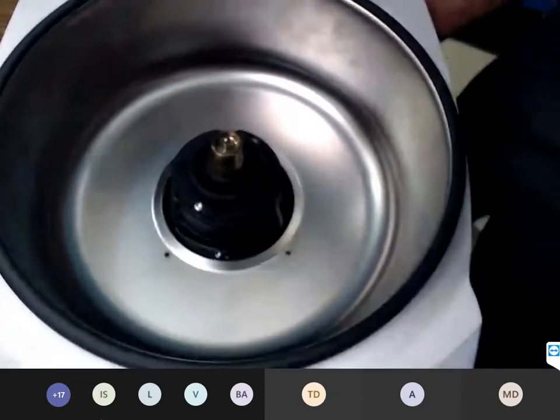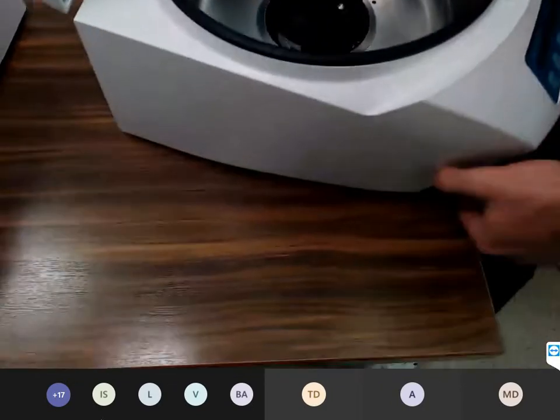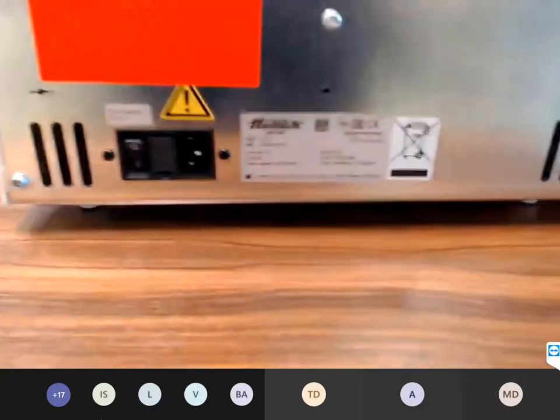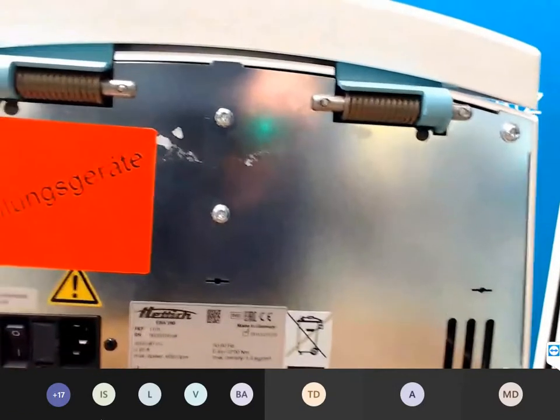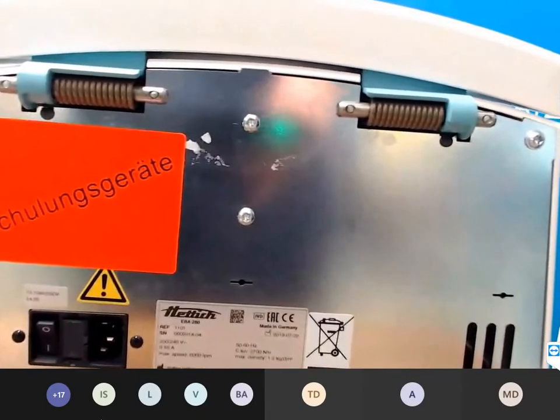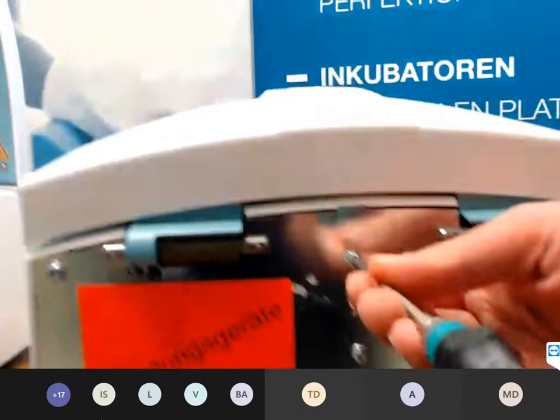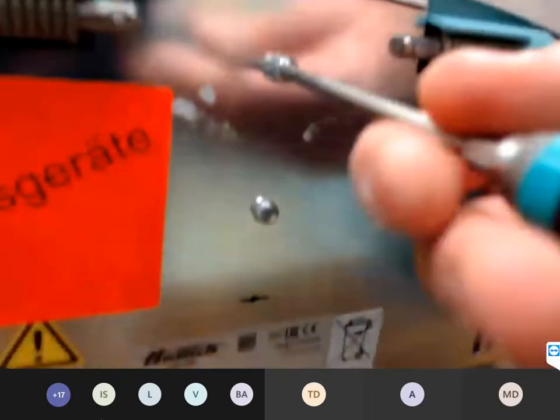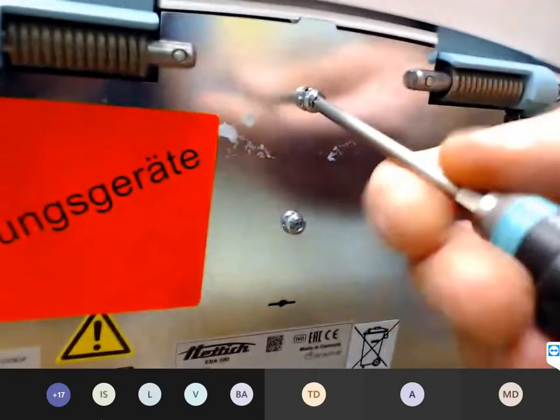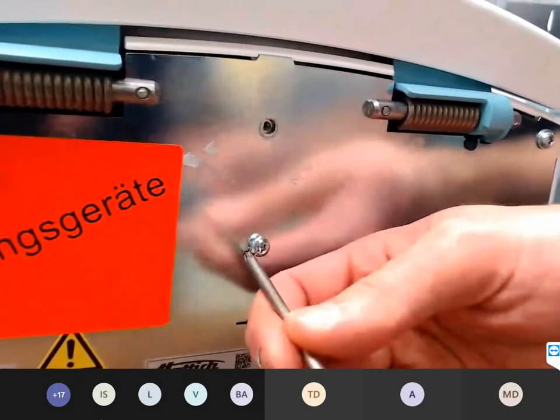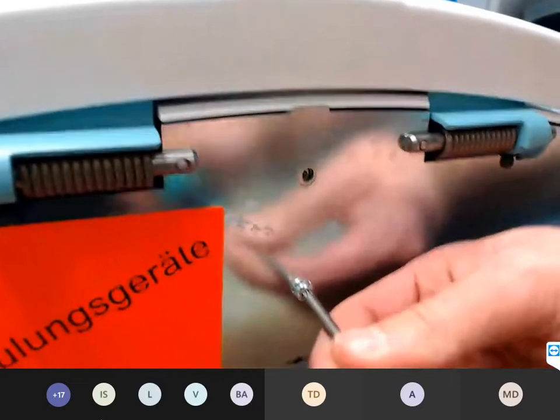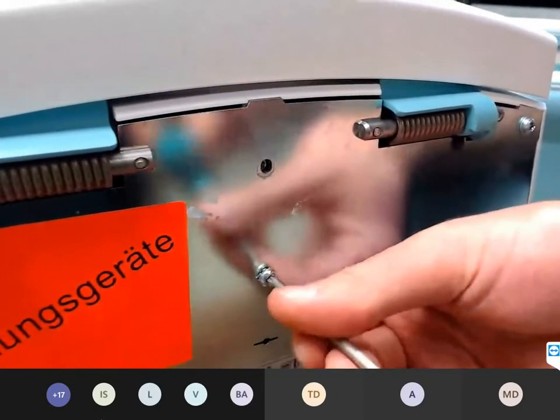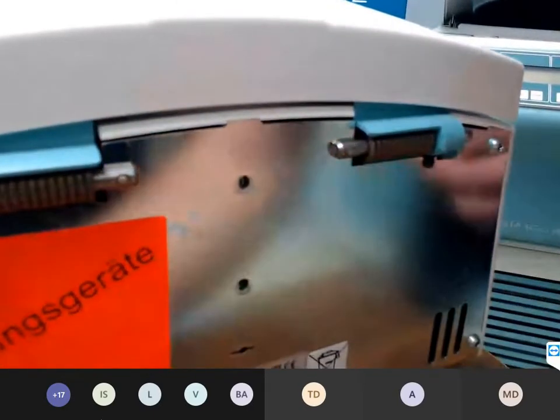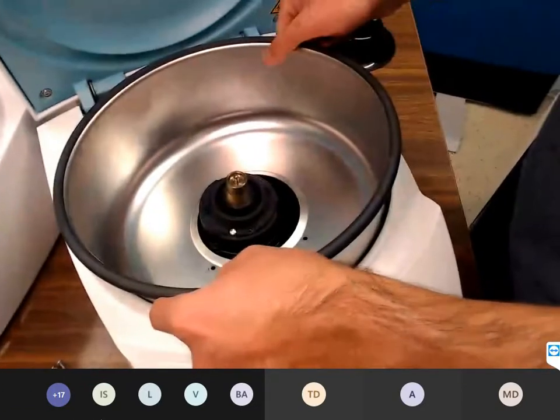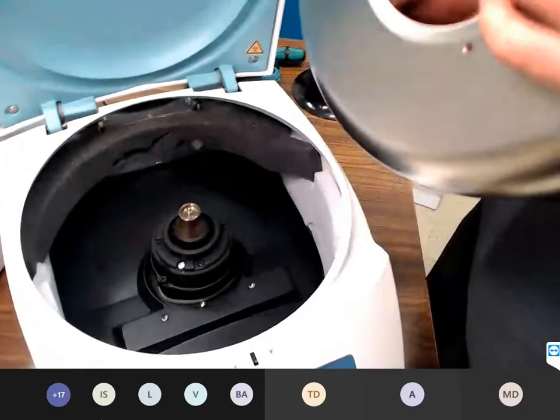Good. The same like the EBA 270. On the back side we have here only 2 screws because, I repeat, we have here not the micro switch for the imbalance detection. We have here also the Hall sensor detection light for the imbalance. Unscrew these 2 screws for the removing of the chamber. And then you can remove the chamber like the EBA, turn to the right side and lift it up.